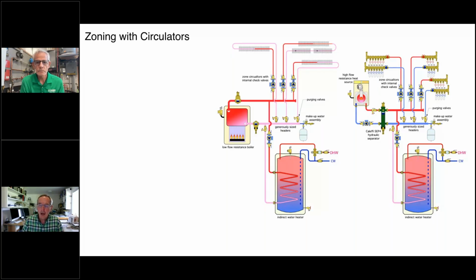Over on the right, we've got another 4-zone system. In this case, it's 3 zones of floor heating and an indirect water heater. You'll see there's a hydraulic separator that separates the headers and the zone circulators from the modulating condensing boiler on the left side, and it's got its own circulator. So this is providing the air and dirt separation. It also is providing magnetic particle separation. So if for whatever reason you have some iron oxide in the system, the magnet will capture that, and the magnet can be removed, and then the fluid that would have that in it can be flushed out the bottom. But what is it doing? It's actually separating the pressure dynamics of the boiler circulator from those of the distribution circulator. So we don't get interference between the circulators. Now, again, we'll be talking about that in more detail.